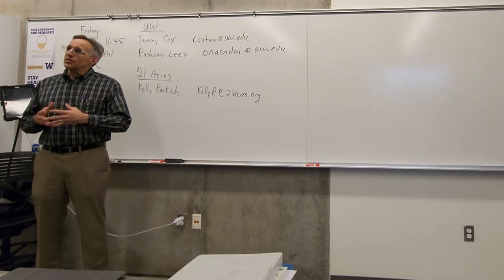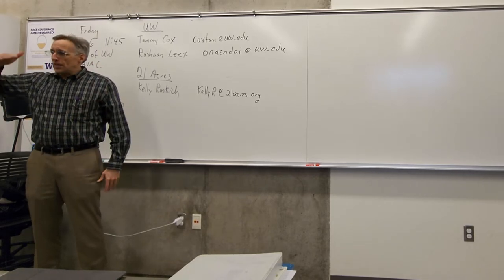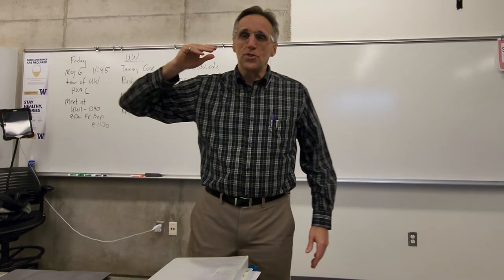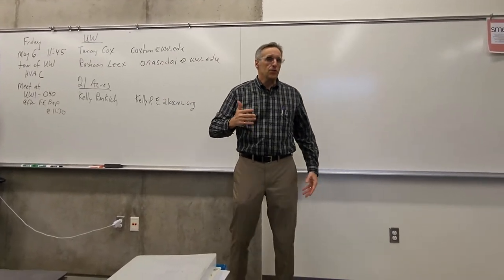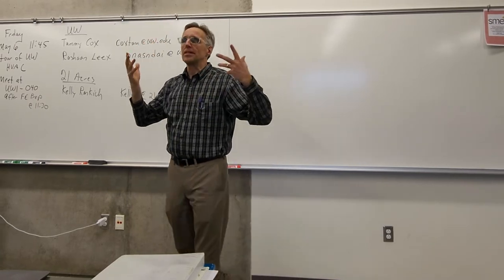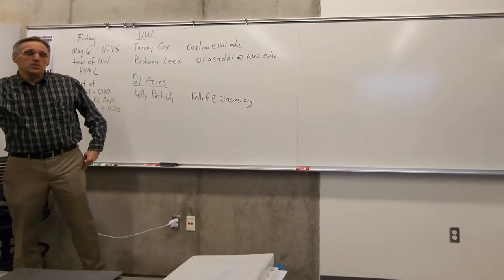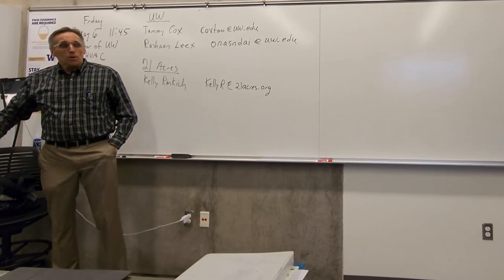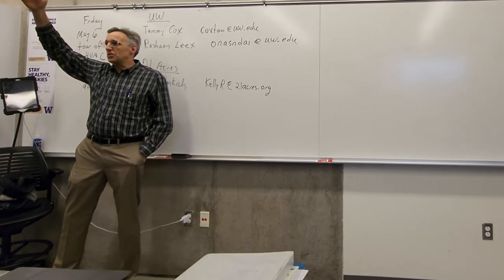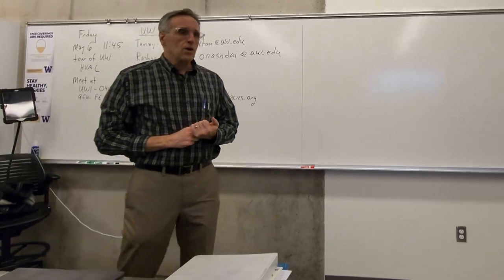I think the big difference for me is that when we're dealing with water, we have to be mindful of elevation change, the elevation head in the Bernoulli equation. That's generally irrelevant with air, because you can move air great vertical distances; air is not dense, so it doesn't really add energy. We don't need energy to move air upward. We need energy to push it through friction in the system. But when we're moving water around, even a 10-foot change in elevation is significant energy. Water is dense, liquids are much more dense. So we have to take the elevation into account.